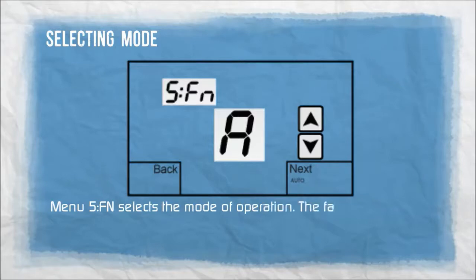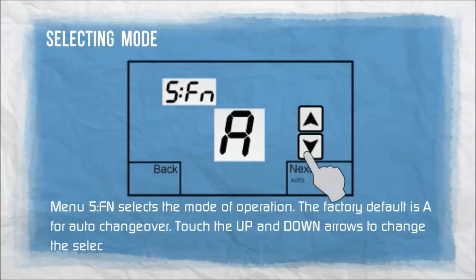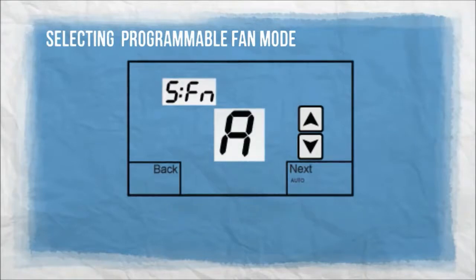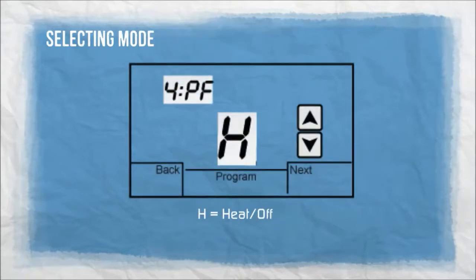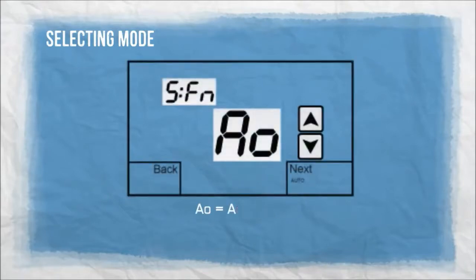Menu 5FN selects the mode of operation. The factory default is A for auto-changeover. Touch the up and down arrows to change the selection. Minus: manual changeover — heat, cool, auto, off. A: auto-changeover. H: heat, off. C: cool, off. AO: auto, off.